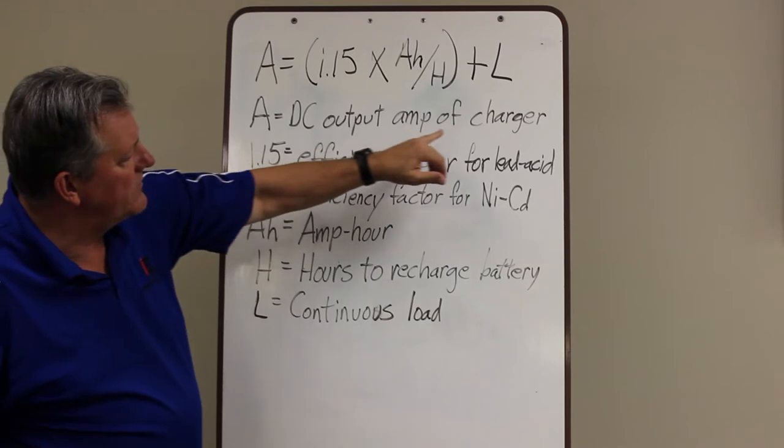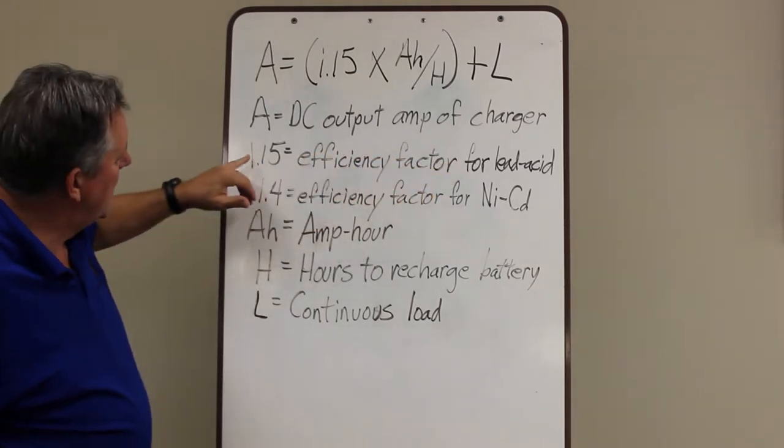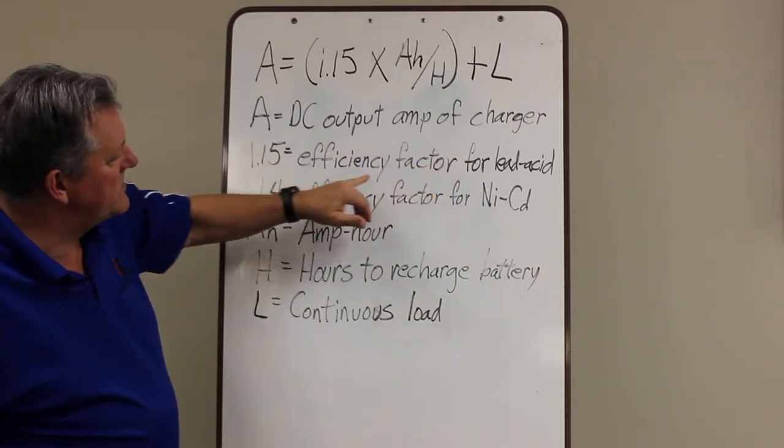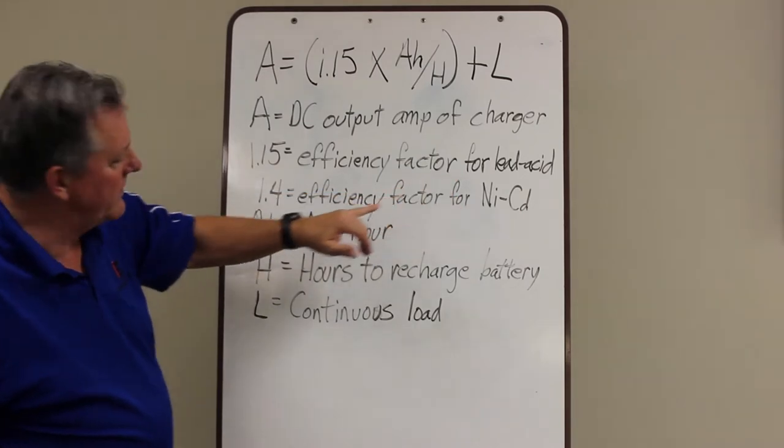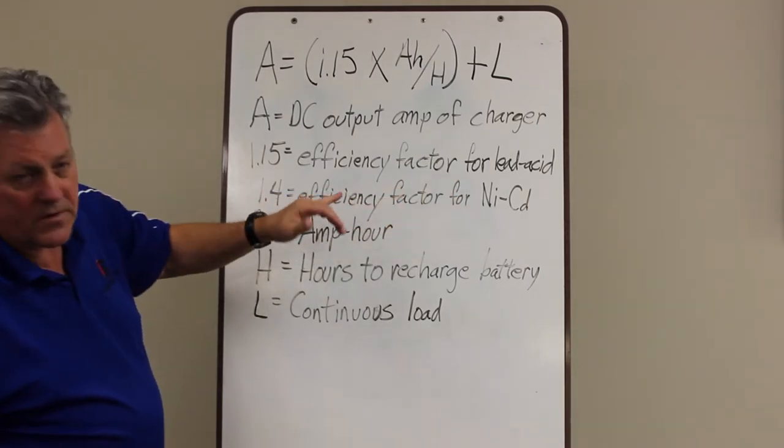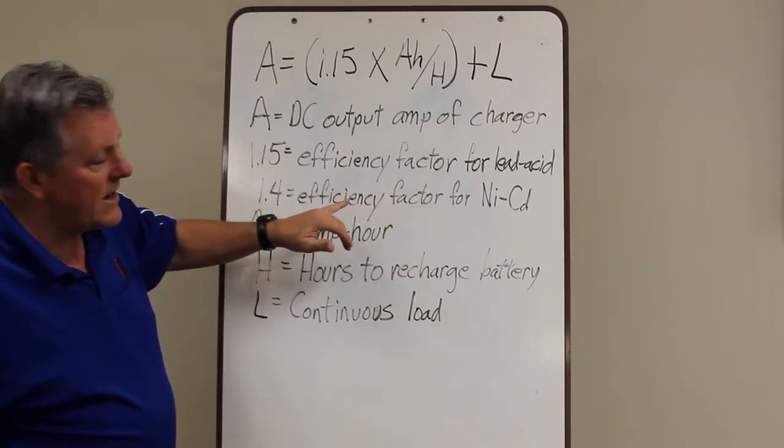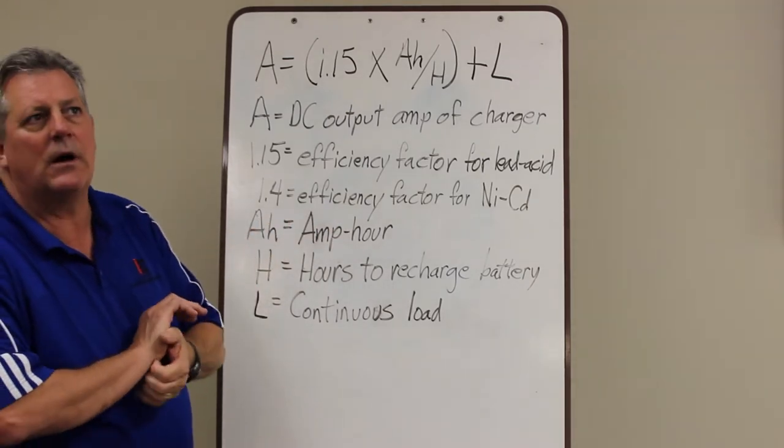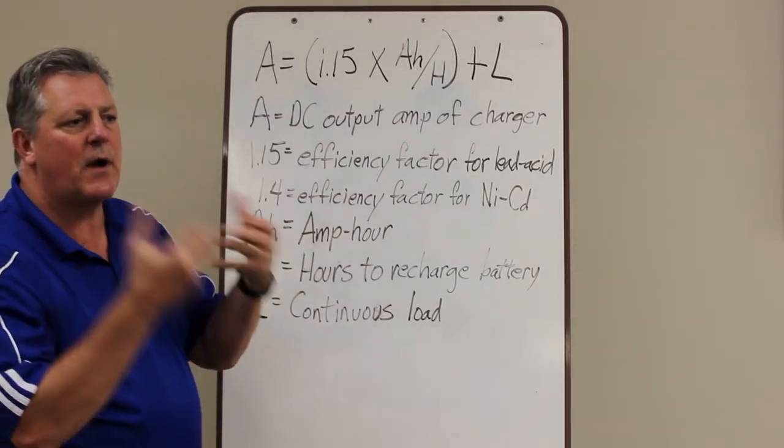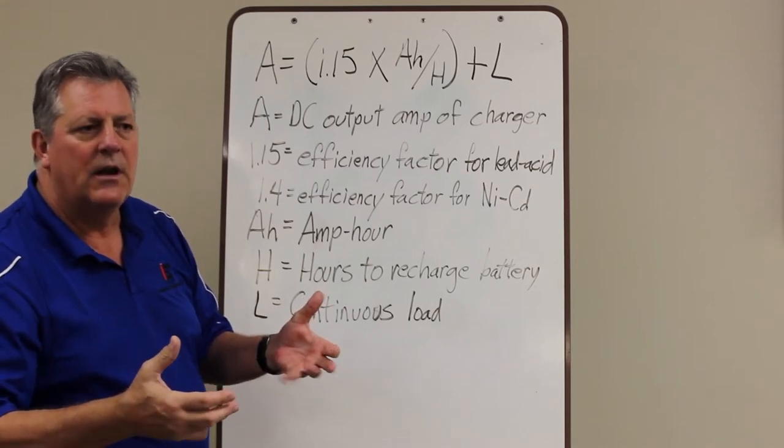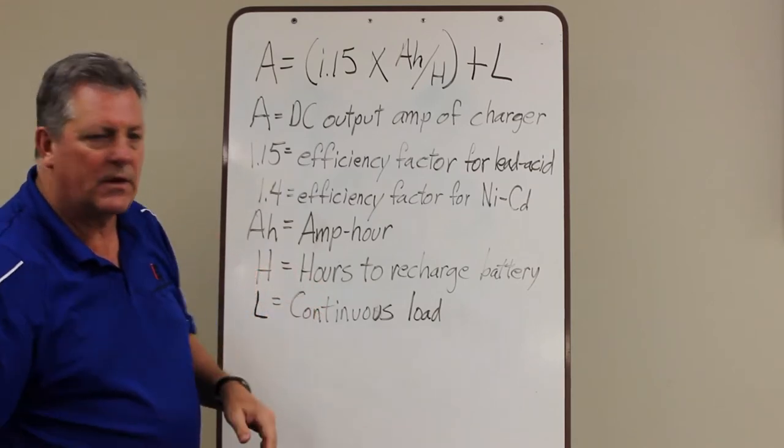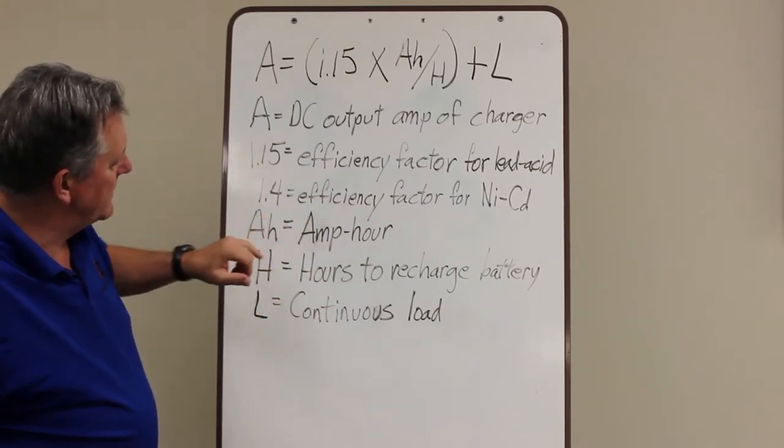A equals the DC output of the charger. That's what you're looking for. 1.15 is the efficiency factor for a lead acid battery. 1.4, that'd be an efficiency factor for a NiCAD battery. That's how efficient, how much power you have to put into the battery to get it to charge up. So each one has a different efficiency ratio.